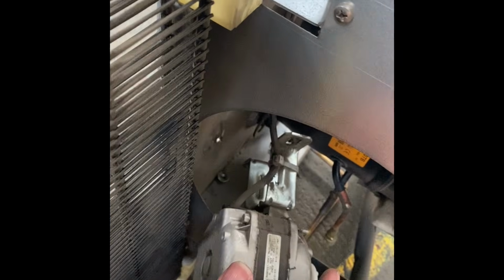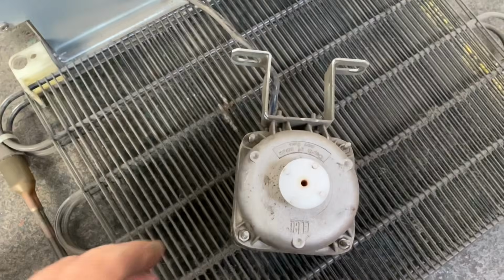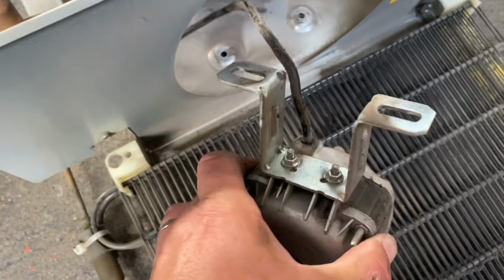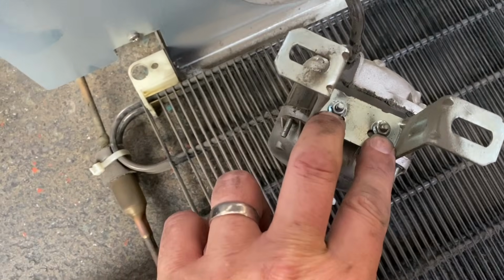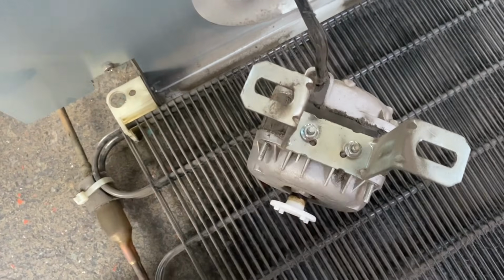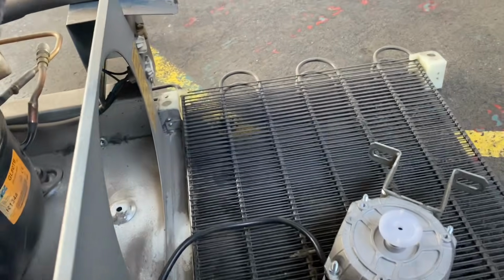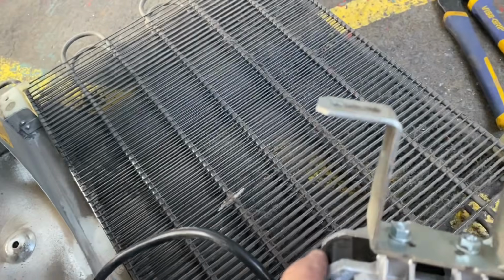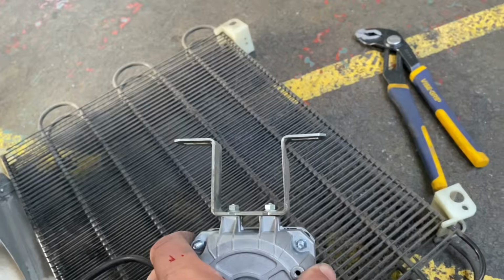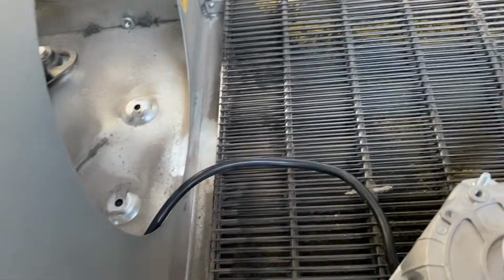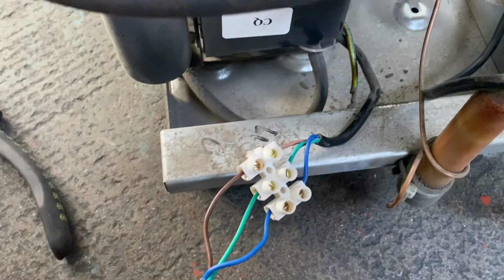The wiring is cable tied to the bracket, so make sure that you take some snips and just snip that cable tie off so you can get it out. Okay, so now if you look, the 2 screws underneath on the new fan motor should match the old fan motor, so you unscrew those and then you put the new fan motor on in its place. Once you've done that, you then need to connect it together.